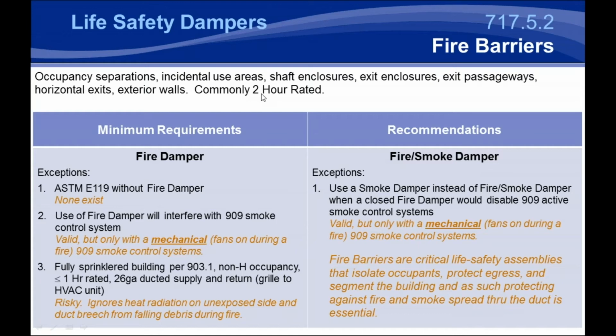As we get to less restrictive barriers, we get to fire barriers that will commonly be 2-hour rated or less. They're used to make occupancy separations, protect incidental use areas, and most commonly shaft enclosures and exit enclosures and passageways. Now, horizontal exits may pass through fire barriers, and we'll talk a little bit about that later in the presentation, as they are commonly misunderstood. But for fire barriers, this is where you first start getting into exceptions for needing fire dampers.